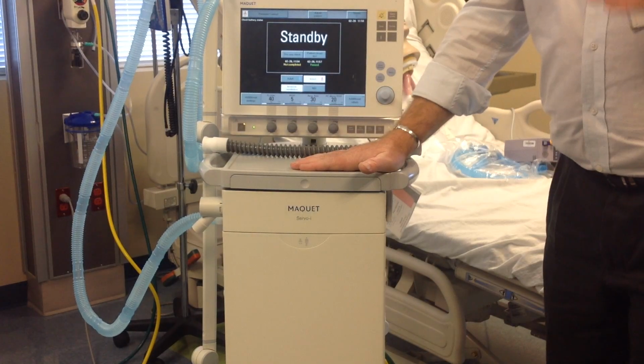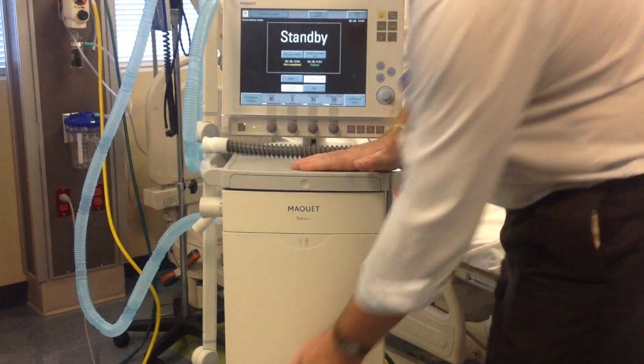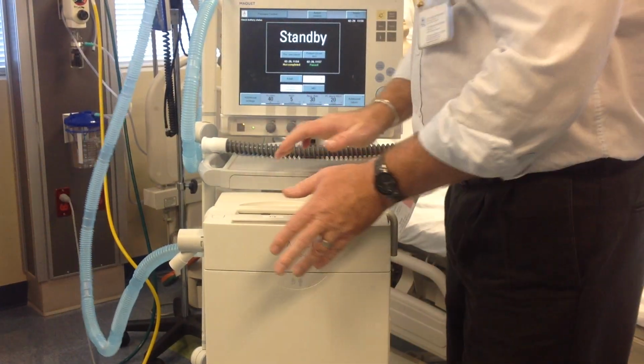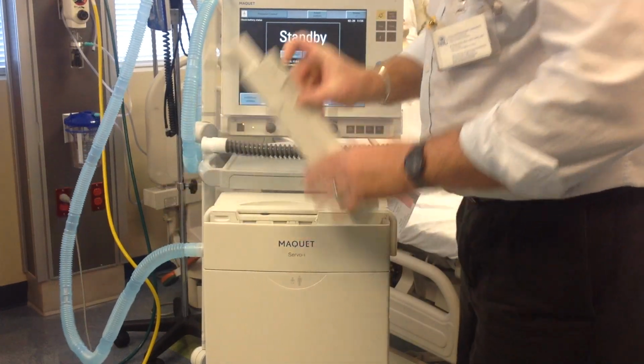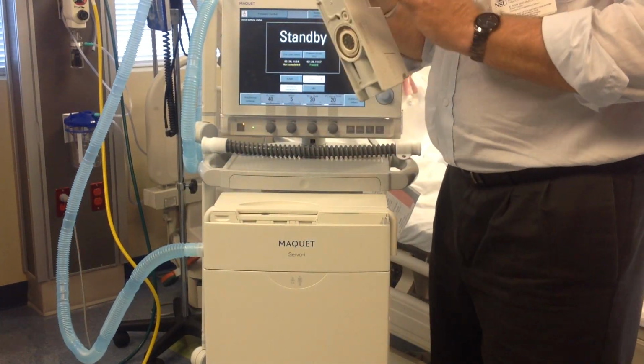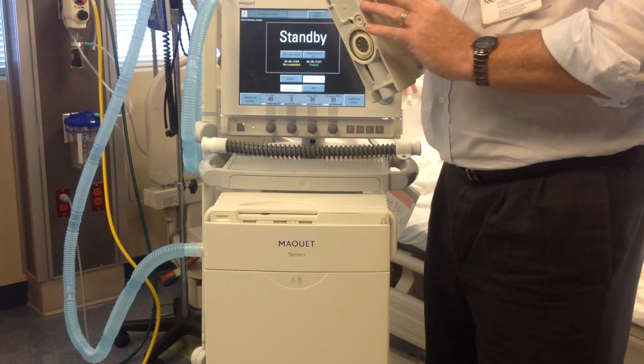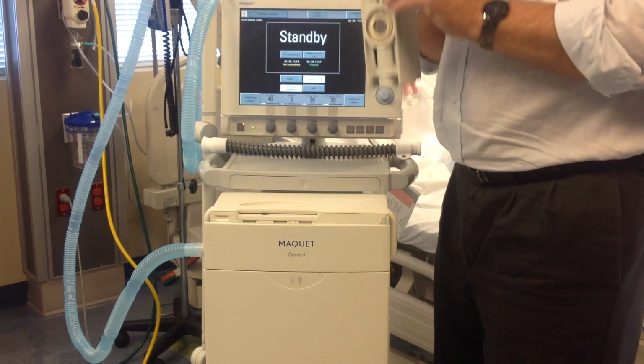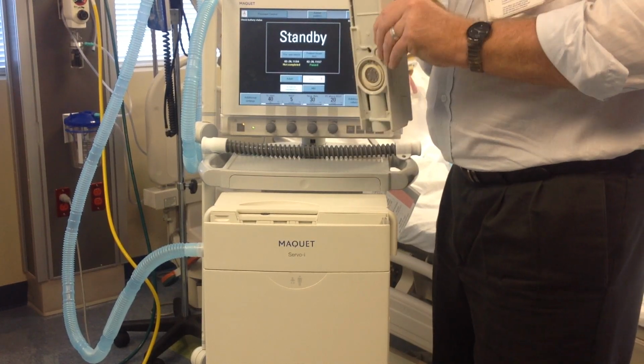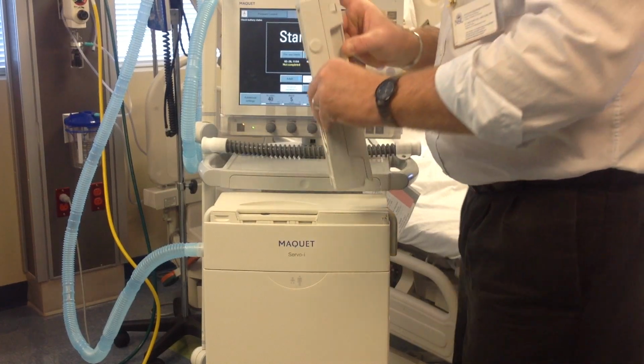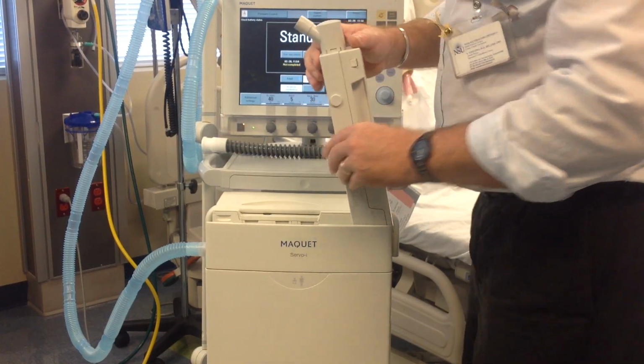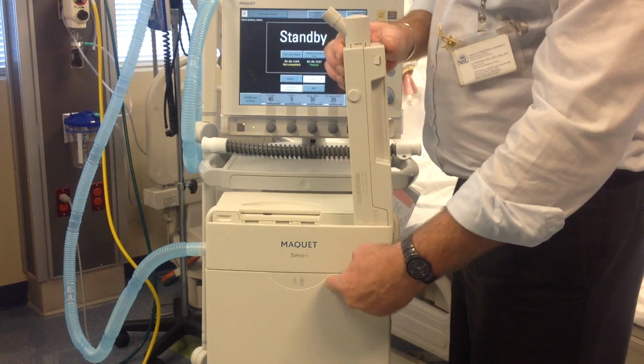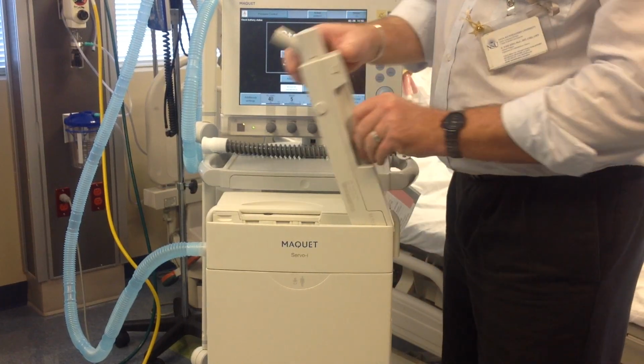Now once you do a pre-use check, this ventilator is now calibrated to this exhalation cartridge. You get water in here, you cannot just change the exhalation cartridge. You will need to do an entire new pre-use check. So right now, right after the pre-use check, this cartridge is with this ventilator.